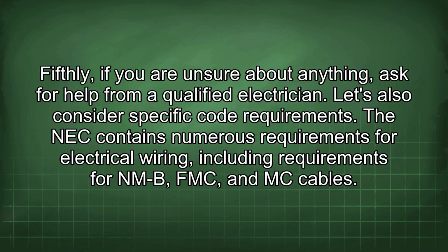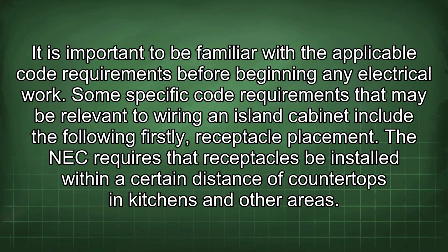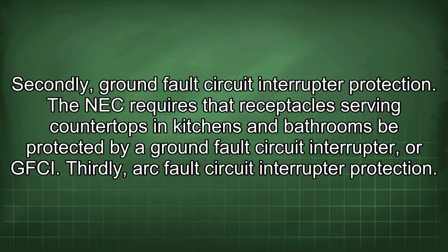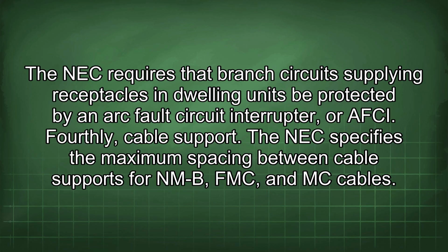The NEC contains numerous requirements for electrical wiring, including requirements for NMB, FMC, and MC cables. It is important to be familiar with the applicable code requirements before beginning any electrical work. Some specific code requirements that may be relevant to wiring an island cabinet include the following. Firstly, receptacle placement. The NEC requires that receptacles be installed within a certain distance of countertops in kitchens and other areas. Secondly, ground fault circuit interrupter protection. The NEC requires that receptacles serving countertops in kitchens and bathrooms be protected by a ground fault circuit interrupter, or GFCI. Thirdly, arc fault circuit interrupter protection. The NEC requires that branch circuits supplying receptacles in dwelling units be protected by an arc fault circuit interrupter, or AFCI. Fourthly, cable support. The NEC specifies the maximum spacing between cable supports for NMB, FMC, and MC cables.